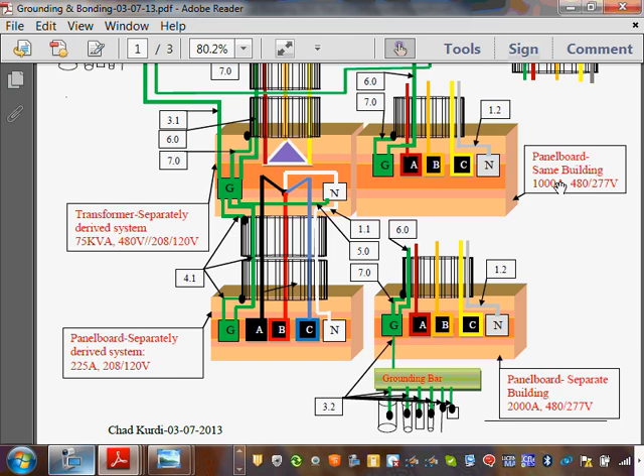Any comments, guys, about these? You're not bonding your neutral to the ground there. Nope. Do you see any bonding of neutral to ground? They're completely separate. Does that still apply on farm sites? On farm sites, when you went to separate buildings, they used to bond that neutral to the ground there and consider it something like a separate service. Now, yeah, these are feeders. Not so when you do farming. There's multiple ways: 3-wire or 4-wire. If you are taking a feeder, you don't bond. If you're taking service conductors, you bond.